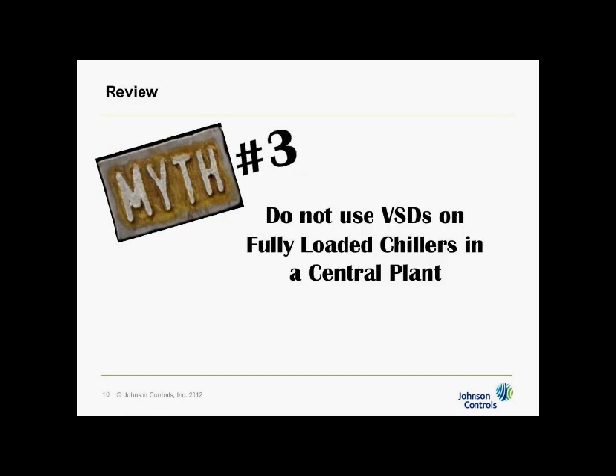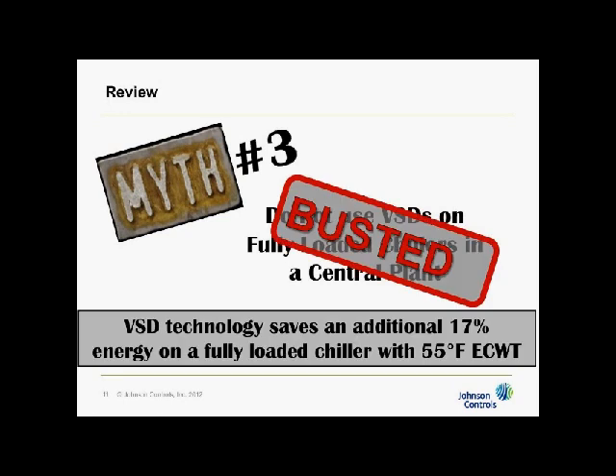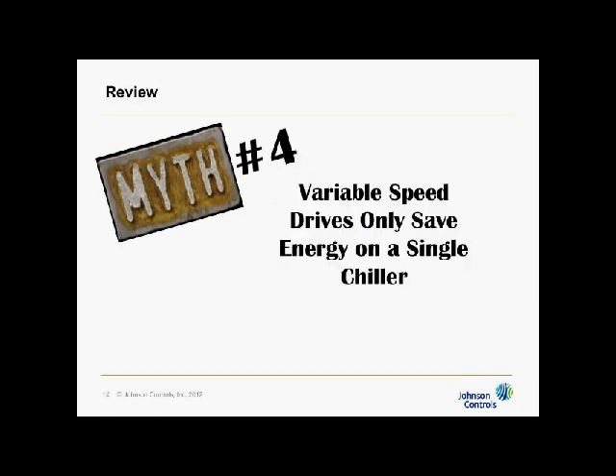Myth number 3, do not use VSDs on fully loaded chillers in a central plant. That one was busted because there's a misnomer, a misunderstanding of what is controlling speed. It is more often head that's controlling speed than load. Where we typically might save 30%, if you can vary both load and head, you can see here at the bottom that I'm saving 17% just on changing head alone, because last time we were strictly looking at 100% loaded chillers all the time. So you can still save because head is a major factor in saving with variable speed drives on chillers. Myth number 4, variable speed drive only saves energy on a single chiller.